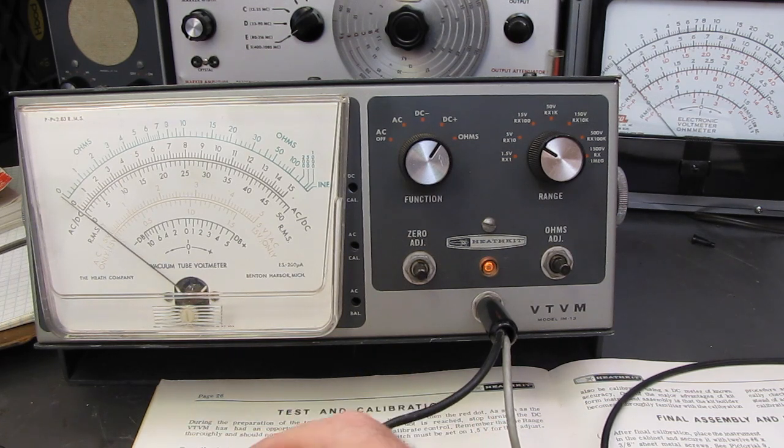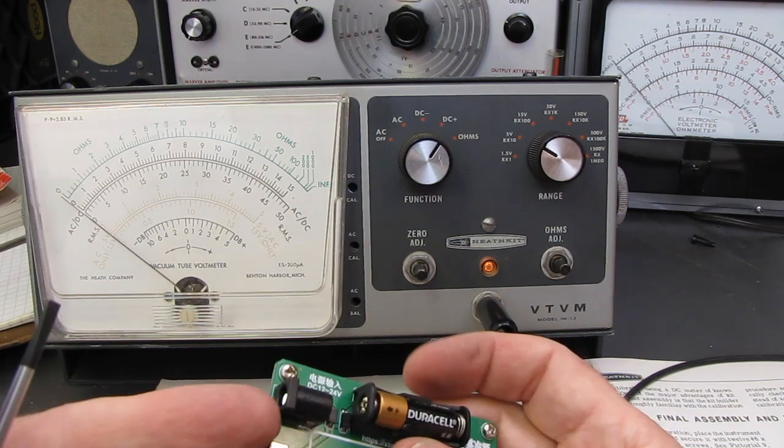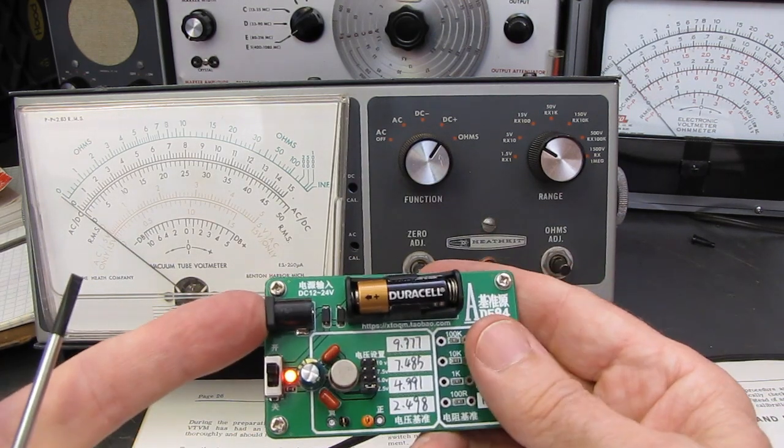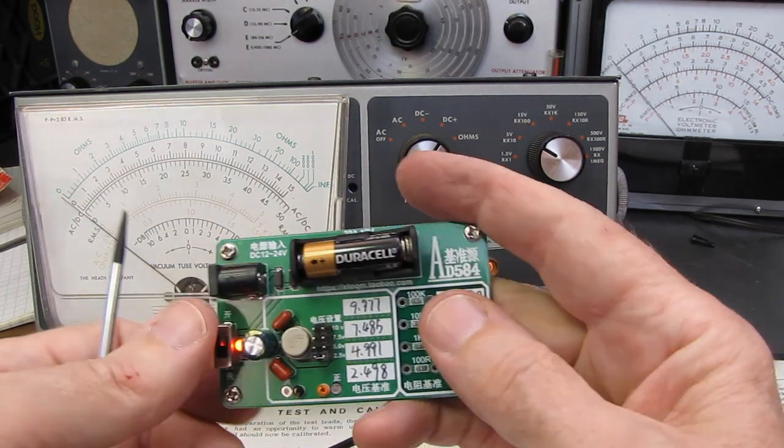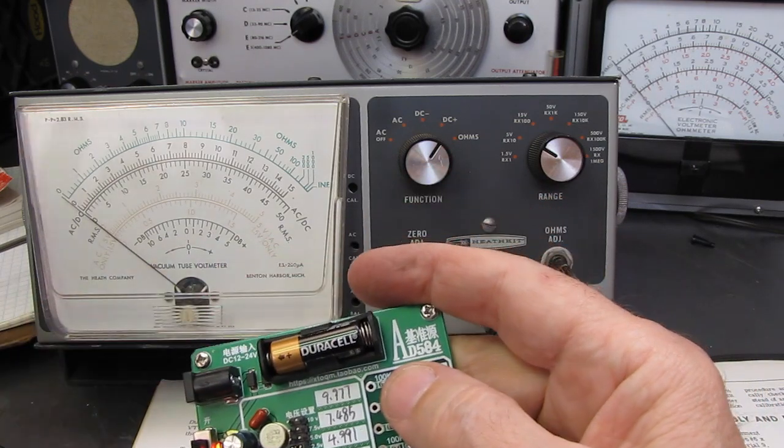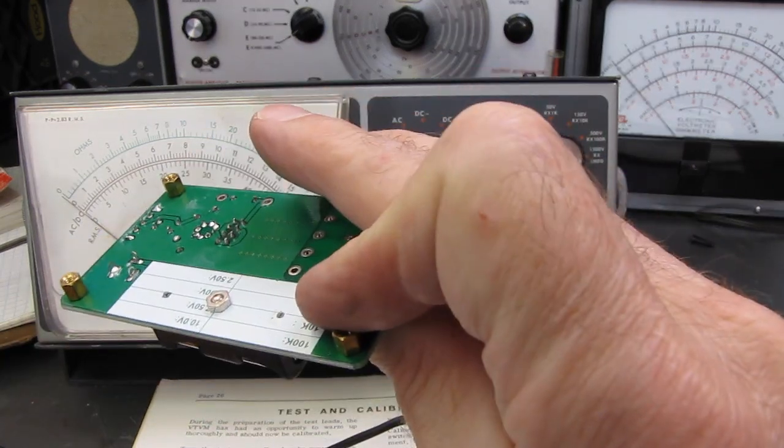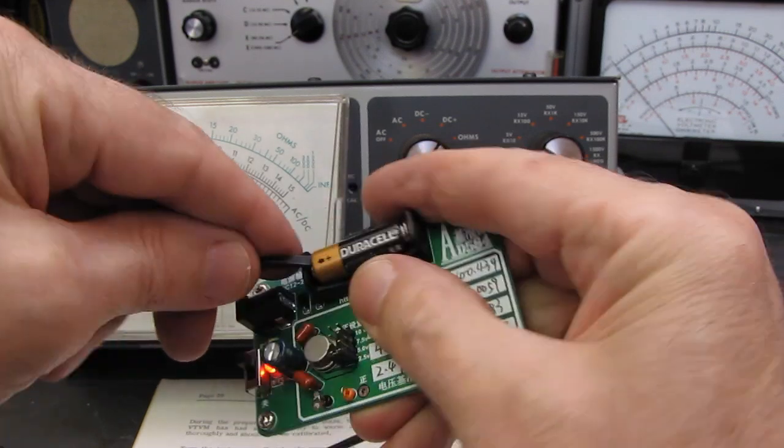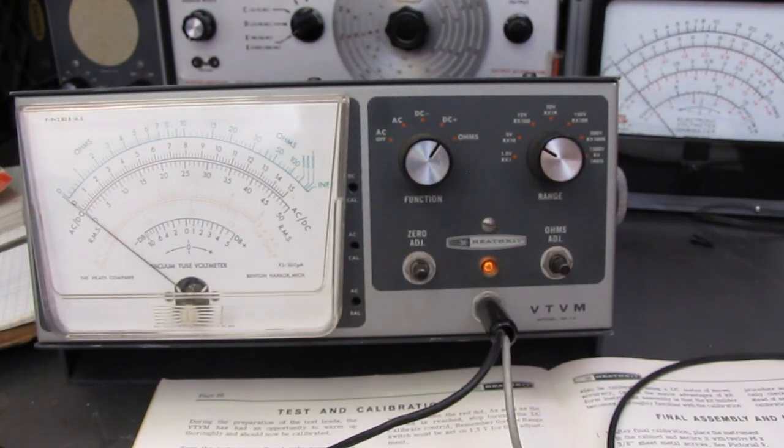Okay. It's a little high. A little bit high. DC Cal. Just like the book says, we're going to tap. 2.498. It's about a needle's width that way and I don't know how it looks in the camera but just about on the money. Two and a half volts. All righty. We'll pull the battery out of this.